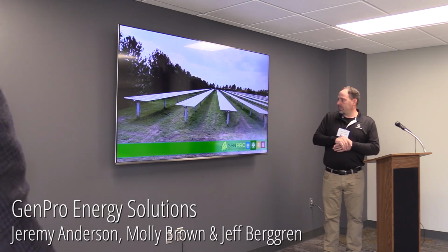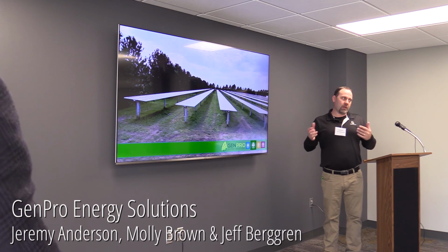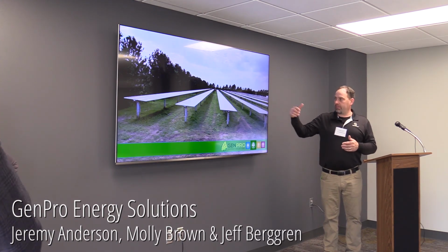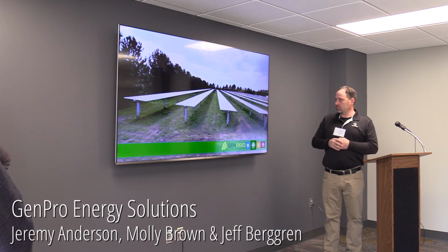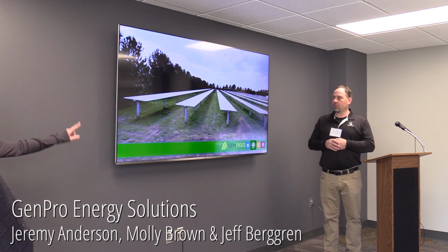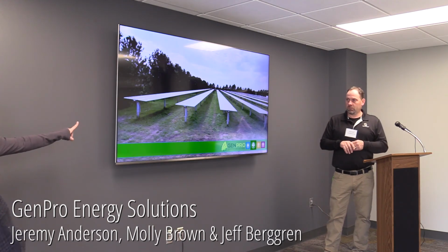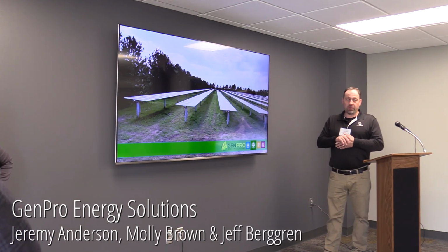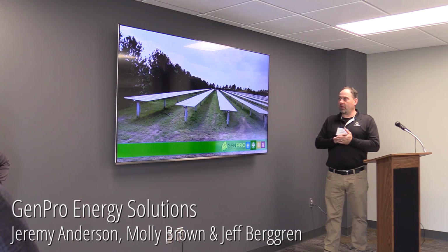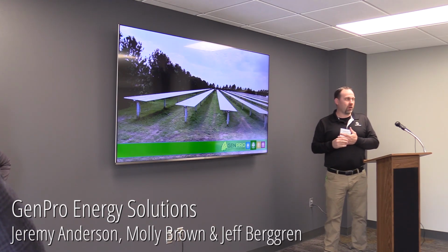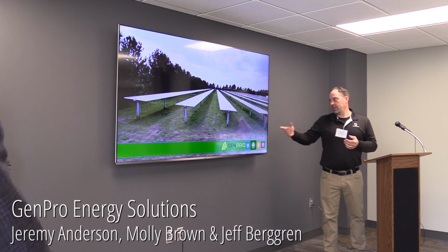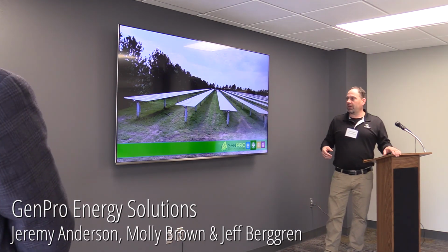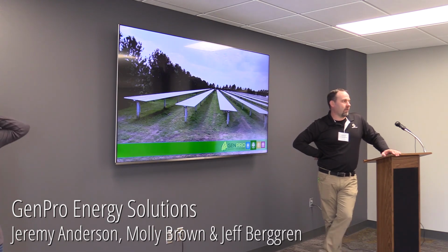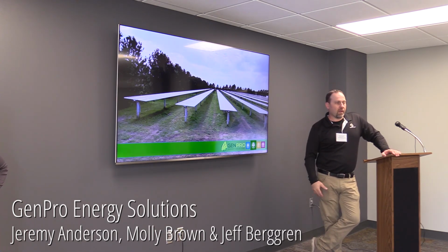And then the modules take about the same amount of time. So you're looking at about 5 more days or so for a 500 kW block to put all the modules on. A lot of times we will hire local temp labor for the module hanging and mechanical hanging portion of that. Yes, we utilize a lot of temp labor. We'll always have our main guys on site, our electrical guys and our guys that know what's going on, but for just brute strength, we need a lot of manpower to do this. They're about 40 pounds a piece, and by the end of the day, you can imagine you get pretty tired if you're hauling them by yourself. Like at Fremont, I think we had about 10 temp laborers and 4 of our guys doing the module portion of it.